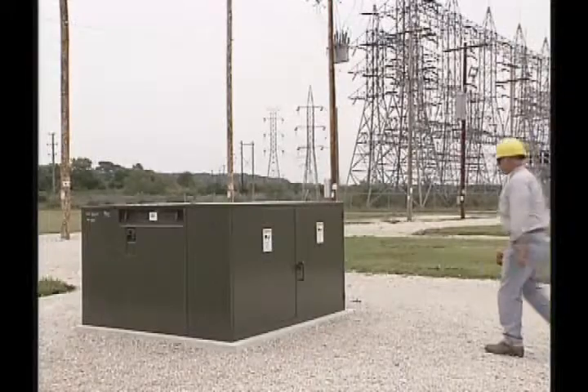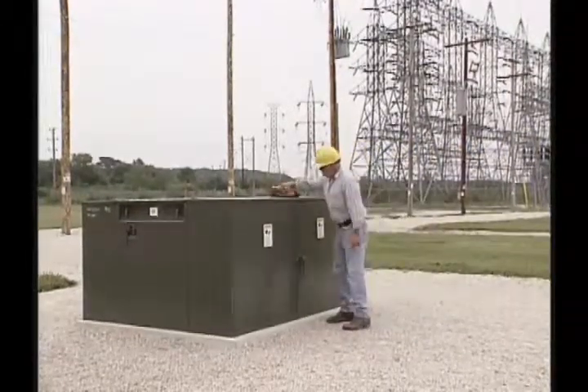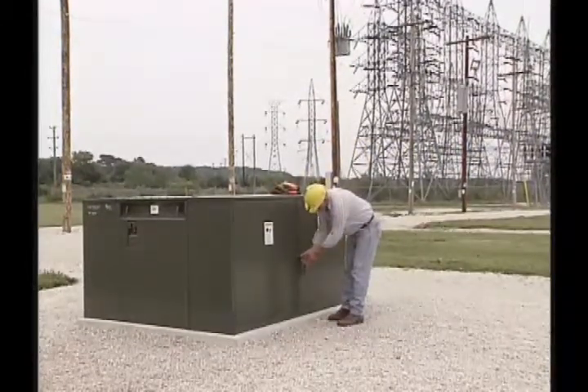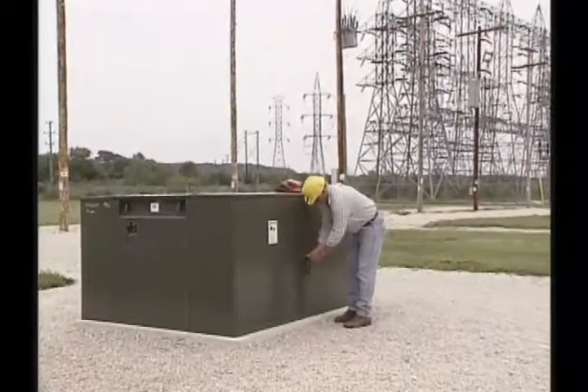VFI vacuum switchgear provides fault interruption and convenient load switching for 15, 25, and 35 kV underground systems. It's available in single-phase and three-phase configurations and is designed for industrial, commercial, and residential applications. VFI switchgear meets ANSI pad-mounted standards for dead front construction and enclosure security. Dead front construction minimizes the high voltage safety hazards for both the operator and the general public.